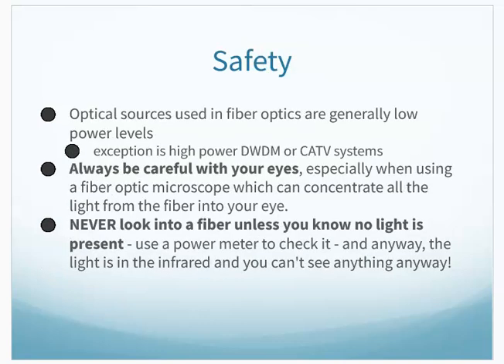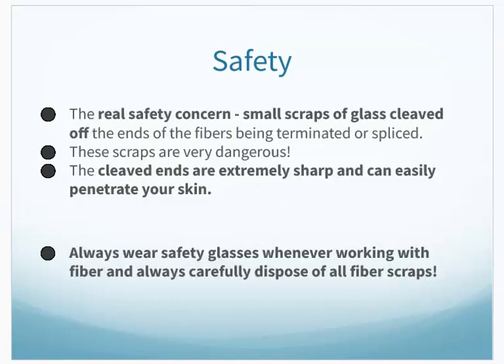When dealing with fiber optic, we have some safety issues to pay attention to. The light sources for fiber optic are generally low power level, not lasers designed to cut through cans or anything like that. However, they are at wavelengths that can do damage, and often at wavelengths we can't see. So I need to be careful about where this light is going. I never want to look into a fiber unless I know it's disconnected and there's no light source on the other end.